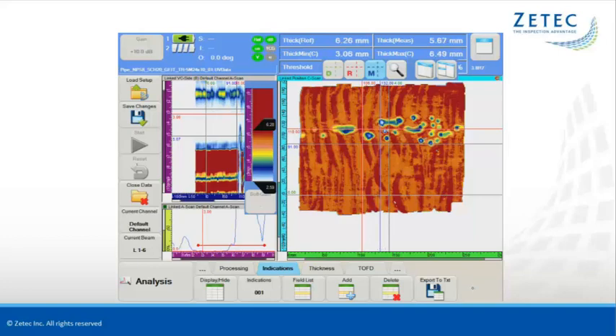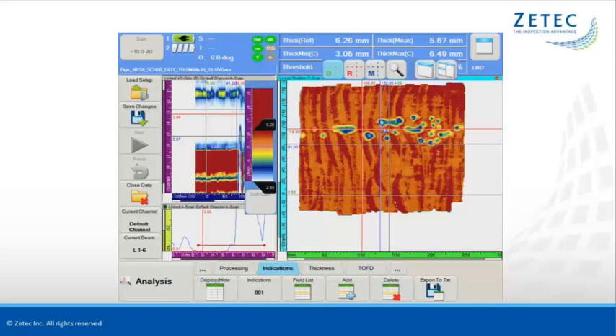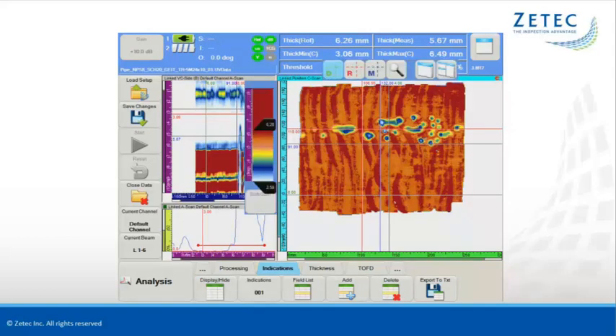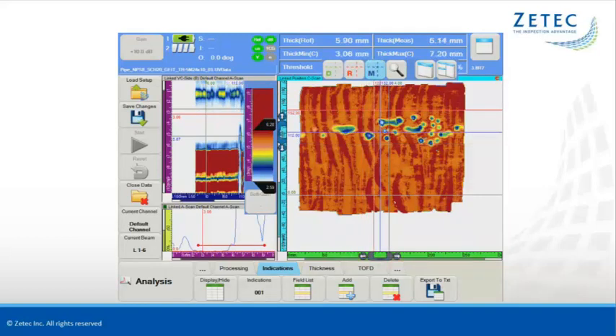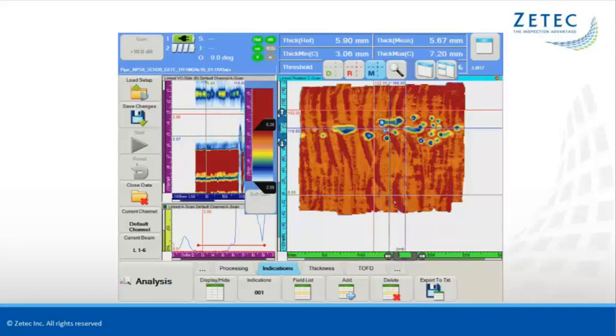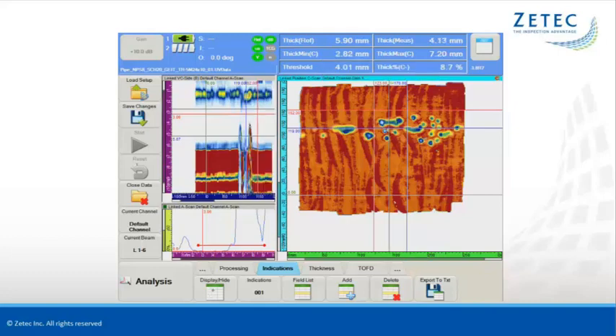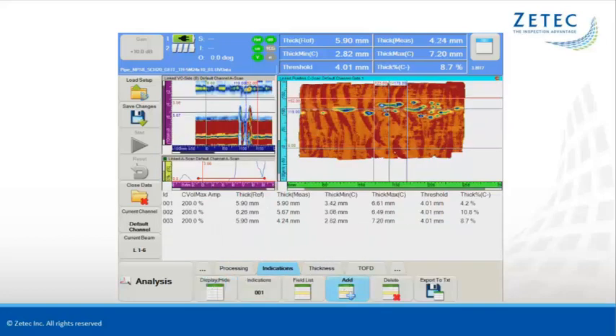Amplitude and Position C scan views are both available for evaluating all aspects of the inspection data. The operator can also use the cursor to measure the remaining wall thickness in specific locations. As the cursors are moved in the C scan view, the corresponding A scan and B scan data are automatically visualized and can be used for more detailed characterization of specific indications.